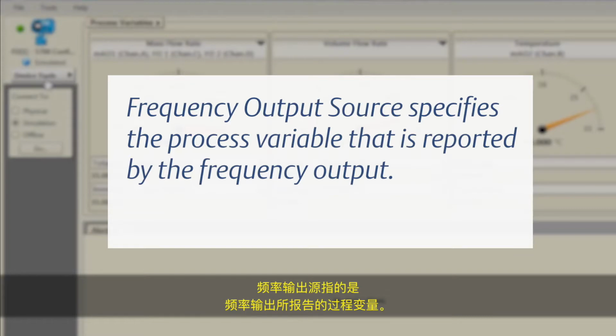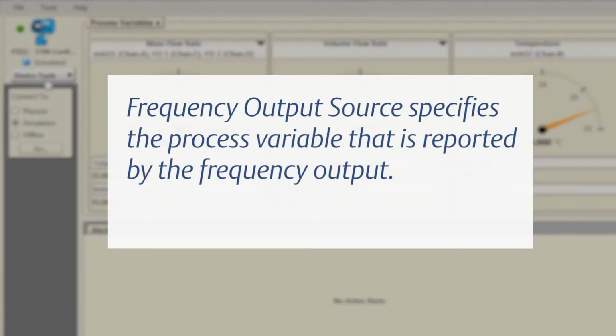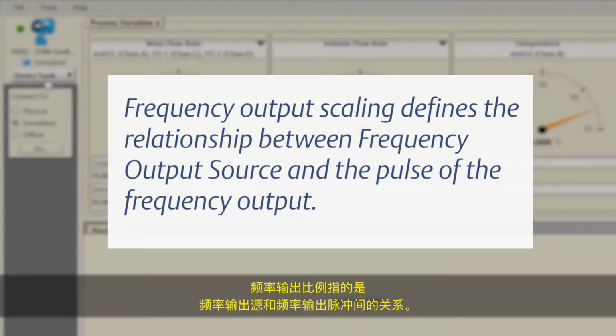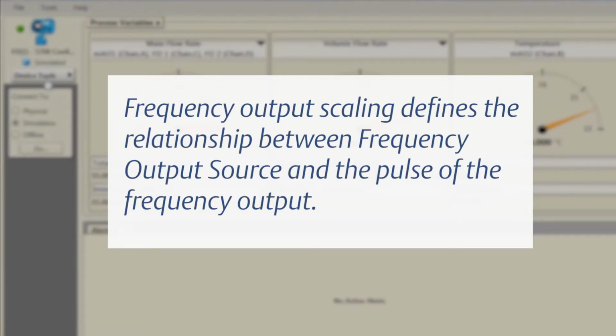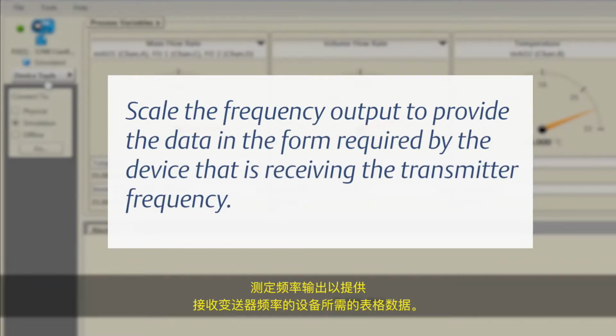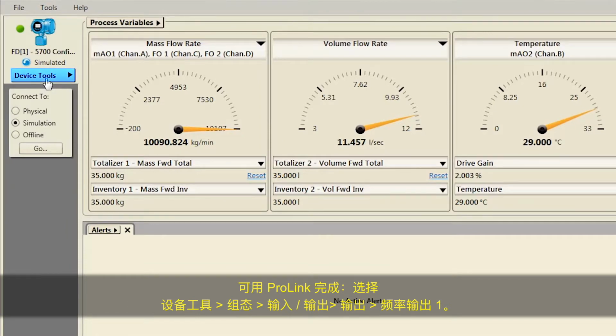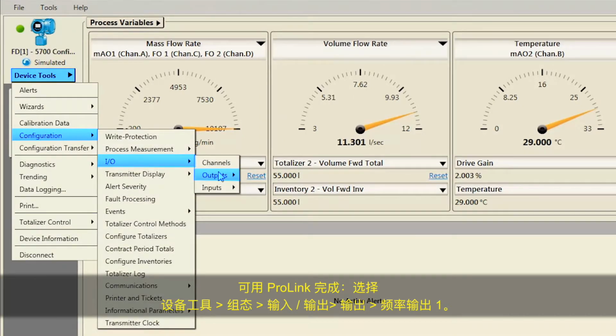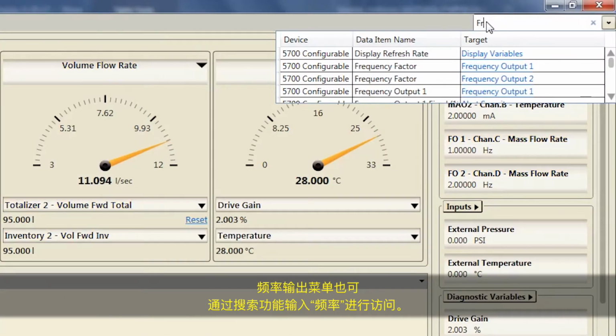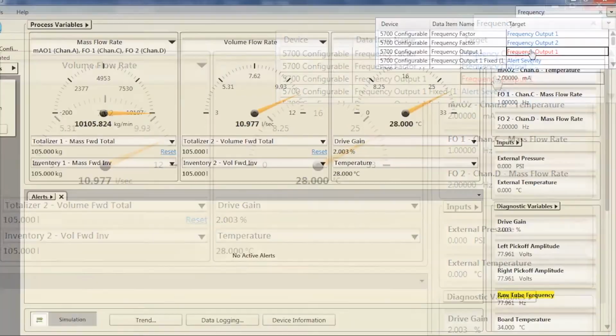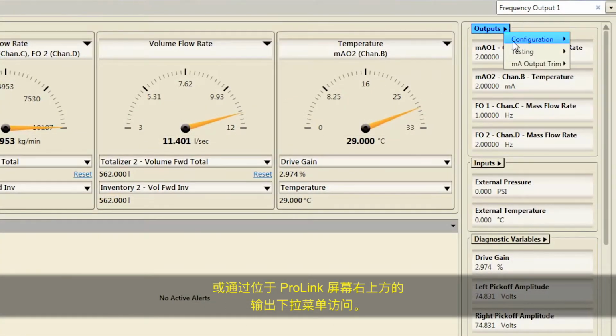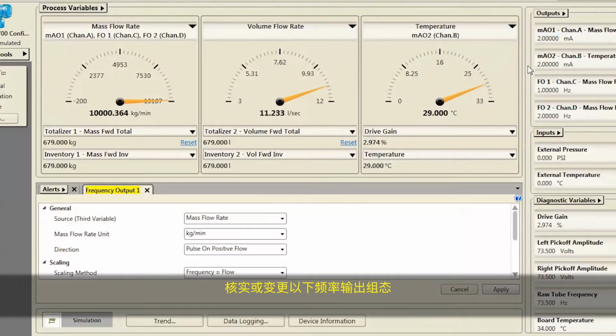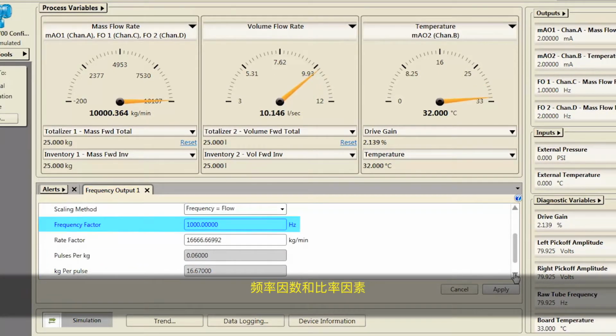Frequency output source specifies the process variable that is reported by the frequency output. Frequency output scaling defines the relationship between frequency output source and the pulse of the frequency output. Scale the frequency output to provide the data in the form required by the device that is receiving the transmitter frequency. This can be completed using ProLink and selecting Device Tools, Configuration, I/O, Outputs, Frequency Output 1. The Frequency Output menu can also be accessed by using the search function and typing frequency or using the Outputs pull-down menu located at the top right of the ProLink screen. Verify or change the following frequency output configuration: source, scaling method, frequency factor, and rate factor.